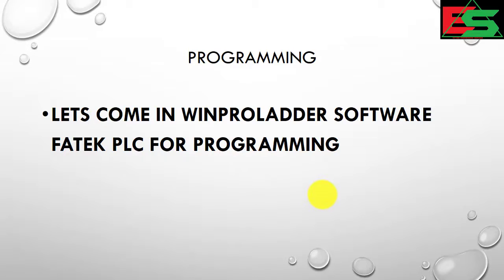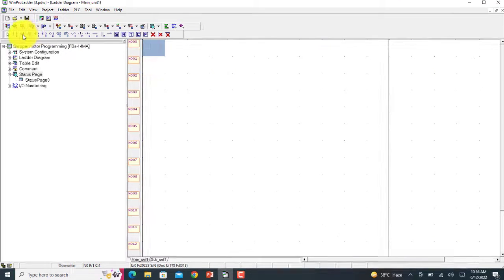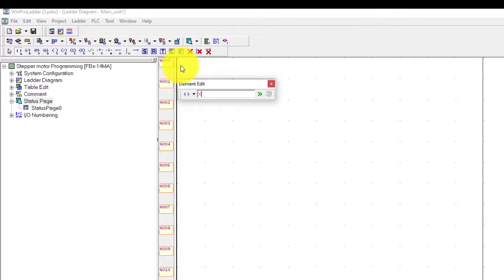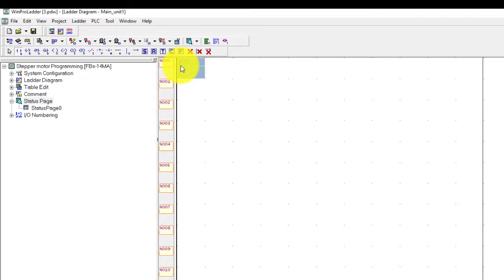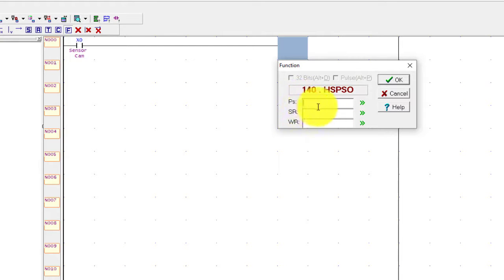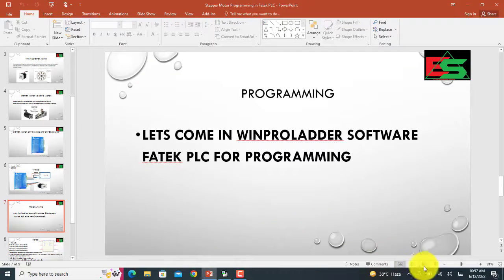Now we will do the programming. Let's open the WinPro software for Fatek PLC programming. I will make one input - input X0. Now I will go to a function; you have to write '140'. This is HSPSO - the high-speed pulse output module or function. We will use this module. There are three inputs: PS, SR, and WR. Let's go to the lecture - I will explain each of these parameters.